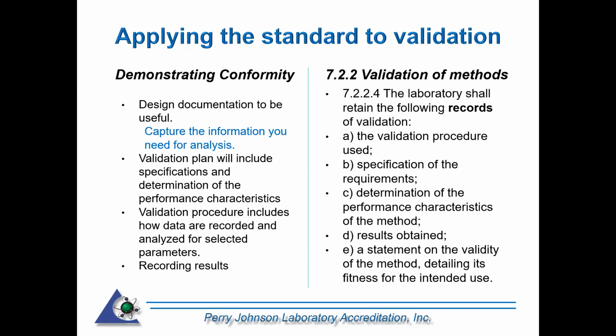You have to have a validation procedure. You must have stated specifications of the requirements. This needs to be recorded. And then as a method is meeting or not meeting the requirements, that should be recorded as well. Determination of performance characteristics of the method, data packages of the results, the actual results that were obtained, and then a statement on the validity of the method detailing its fitness for the intended use.